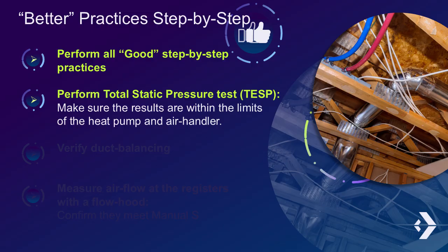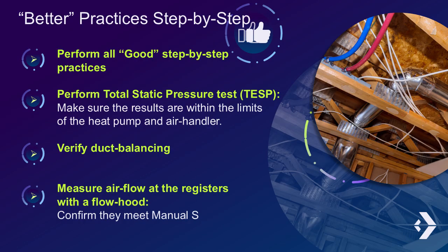Next, verify duct balancing. Similar to TESP, you can perform this test on the system as is during the assessment phase, but it's essential to do it during commissioning. Proper duct balancing ensures airflow is distributed evenly throughout the home, preventing hot or cold spots. Finally, measure airflow at the registers using a flow hood. This step confirms that the airflow meets Manual S requirements. Like the previous tests, airflow measurements can be used as both a diagnostic tool during assessment and as part of commissioning after changes have been made.